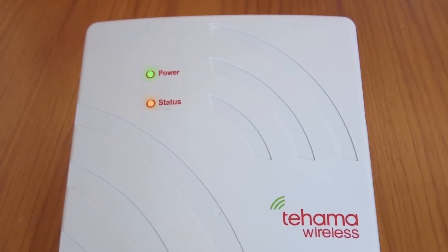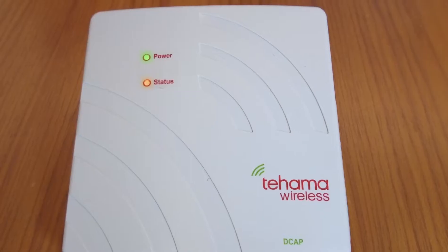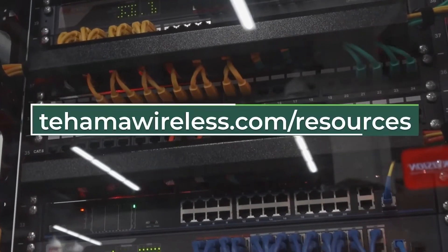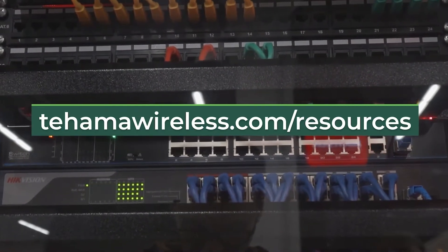If the status light remains orange, the DCAP is not reaching the Tehama servers. In this case, check the cables and the internet connection. If the status light remains orange, in rare cases there may be settings in the firewall or router that restrict the DCAP. Follow this link to the application notes section of the Tehama Wireless website where you can find some troubleshooting steps.